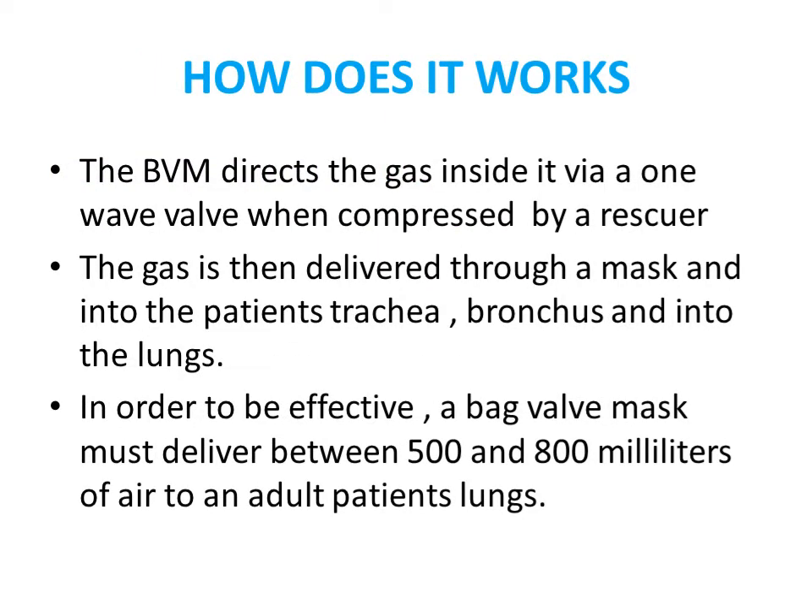How does it work? The valve directs gas inside through a one-way valve when compressed by the rescuer. Gas is delivered through the mask and into the patient's trachea when the bag is compressed, inflating through the trachea and into the lungs. For effective ventilation, the bag-valve must deliver between 500 and 800 milliliters of air to the patient's lungs.